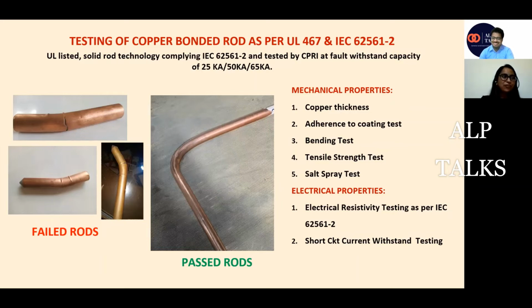If I go with any metallic conductor and say test it at so and so fault current, they will do that also because it is a lab, and it will do whatever we ask. So they will obviously test the pipe and the plate conductor also, because they are metallic, so they will carry the fault current. But the thing which plays an important role is the material which will be installed below the ground, because as long as that material exists below the ground, it will help me in achieving better earthing. If my earthing conductor has corroded after installation, there will not be any conductor and it will not serve the purpose of protecting my equipment. So choosing the correct material is a very important thing when we are talking about the earthing system.